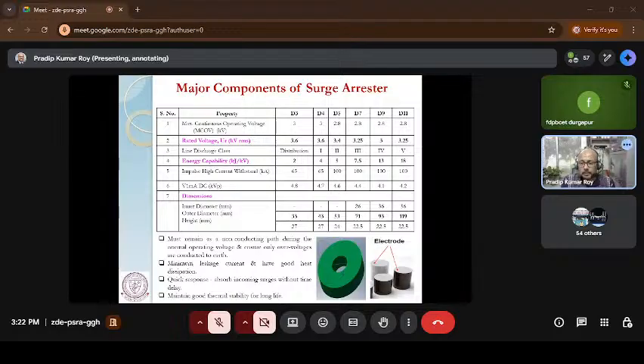The hole is given because the heat which is normally generated during the surge is immediately dissipated after the surge goes back. Otherwise, in the big size, it is very difficult. If we make these solid blocks, it's not easy to dissipate the heat immediately.